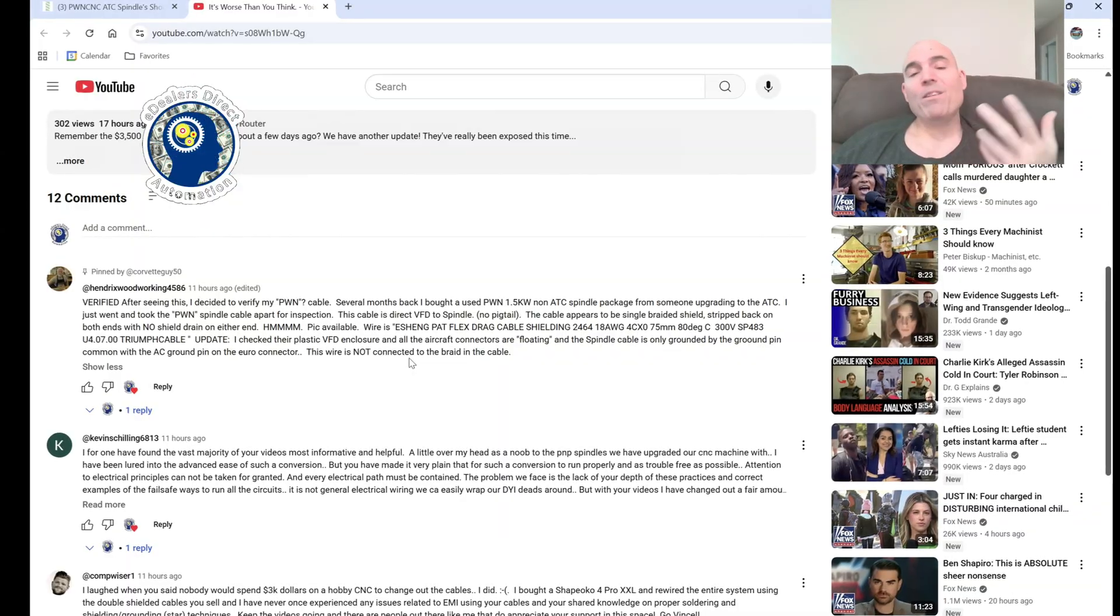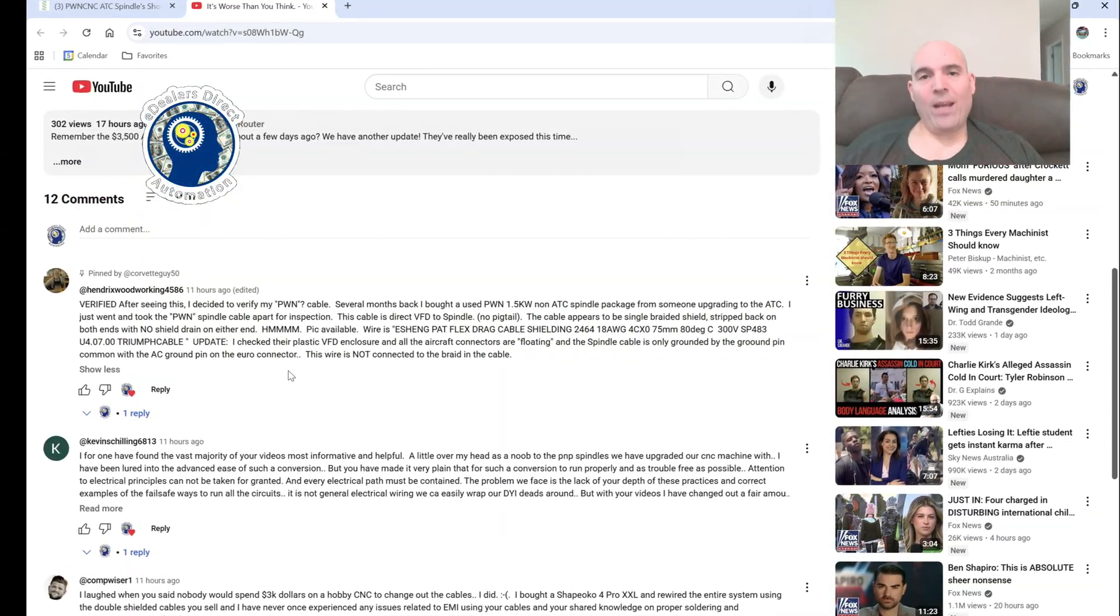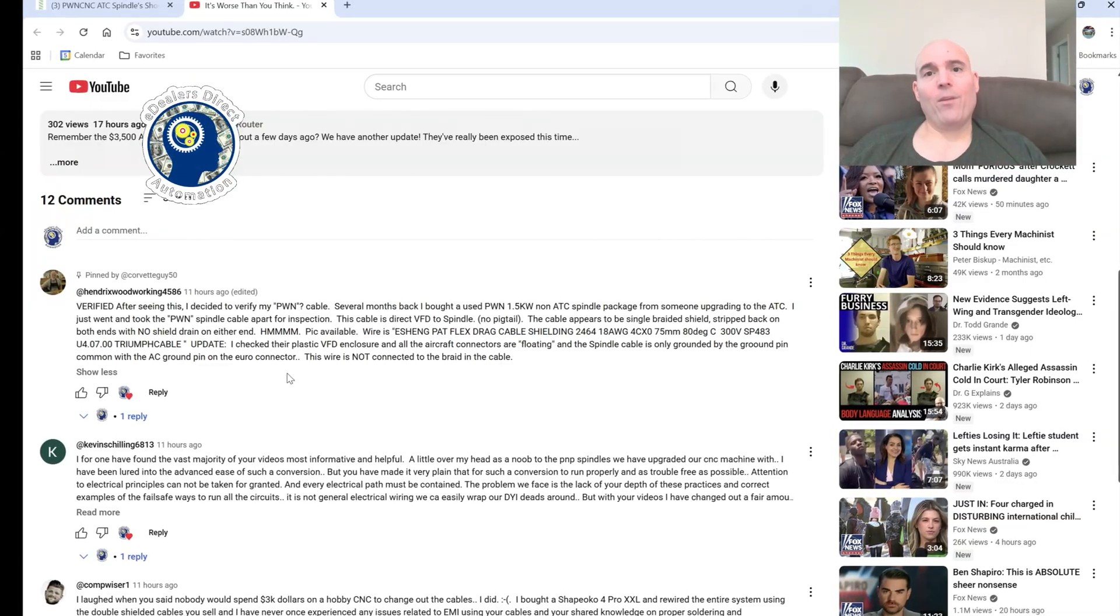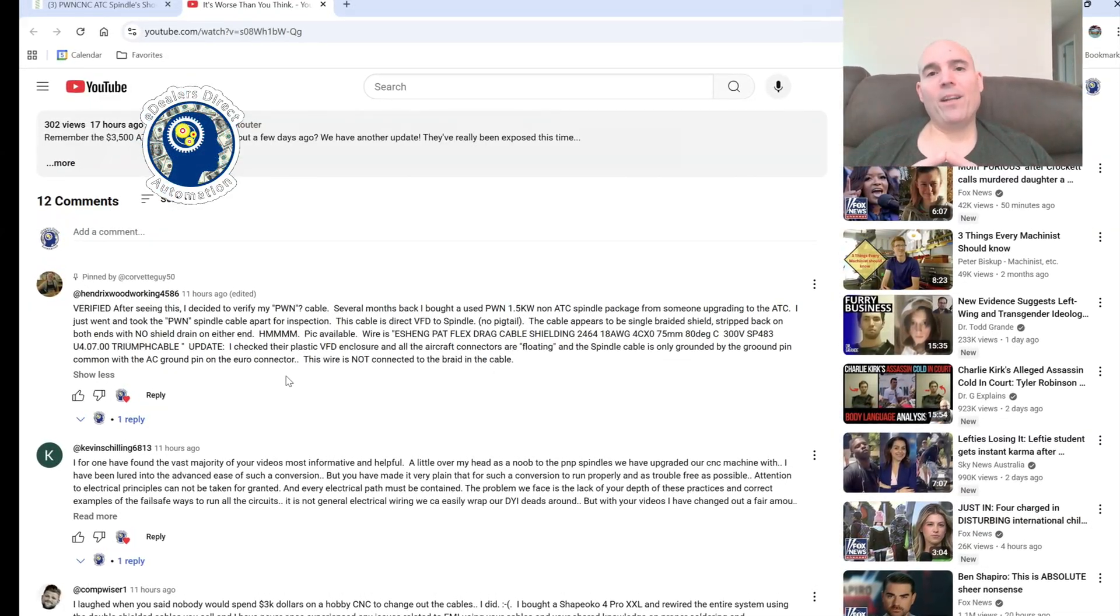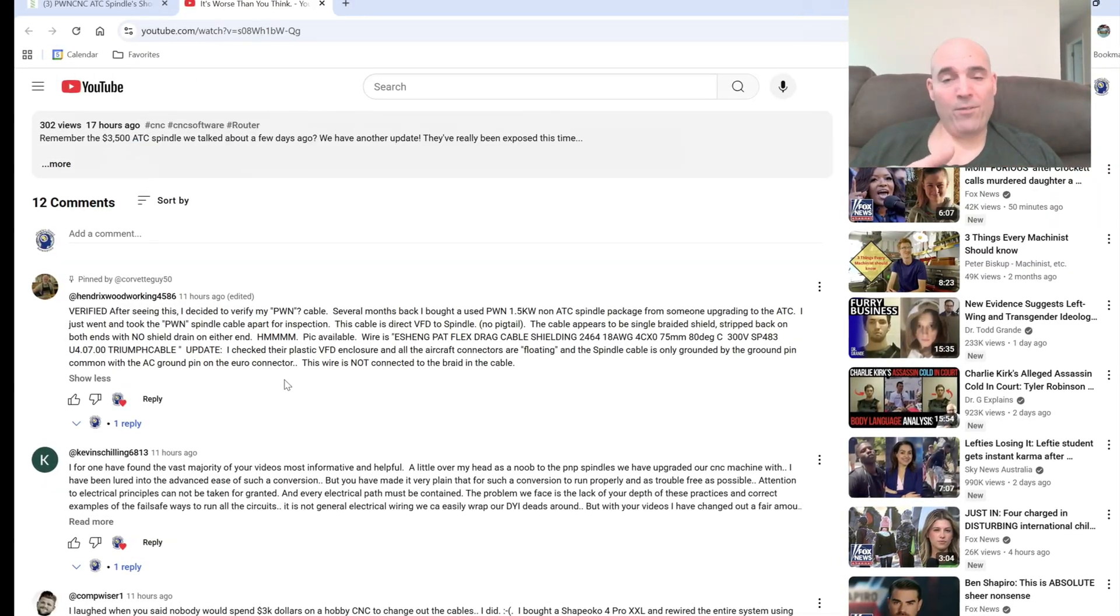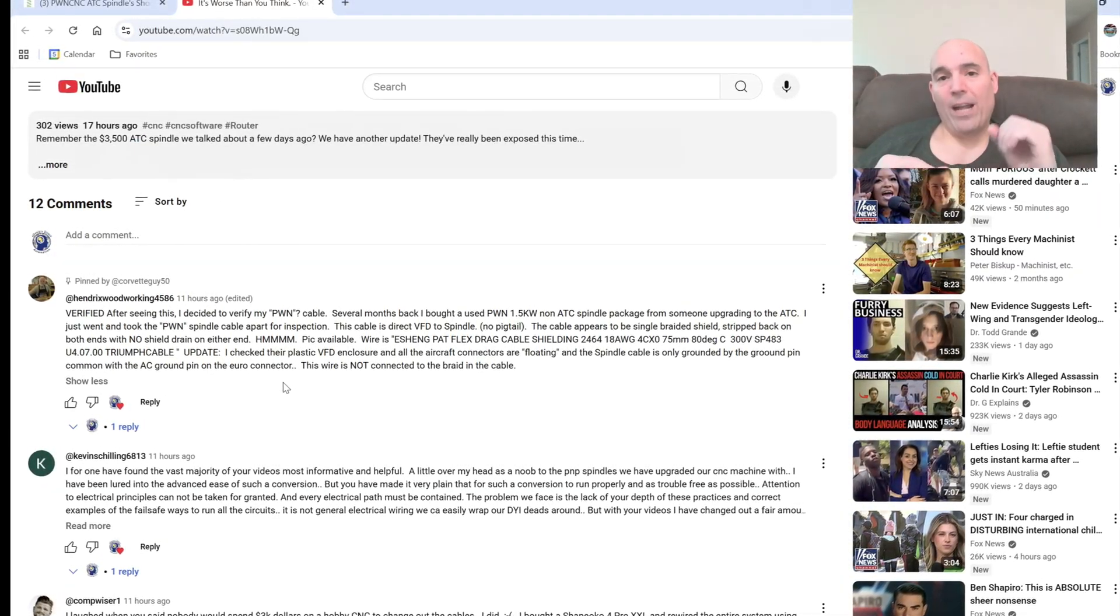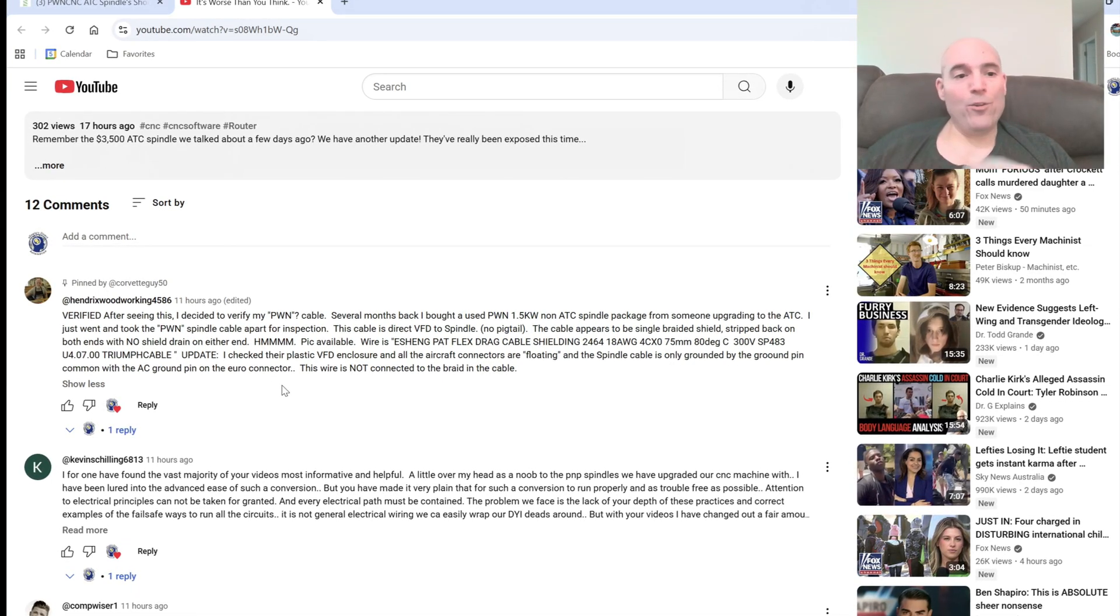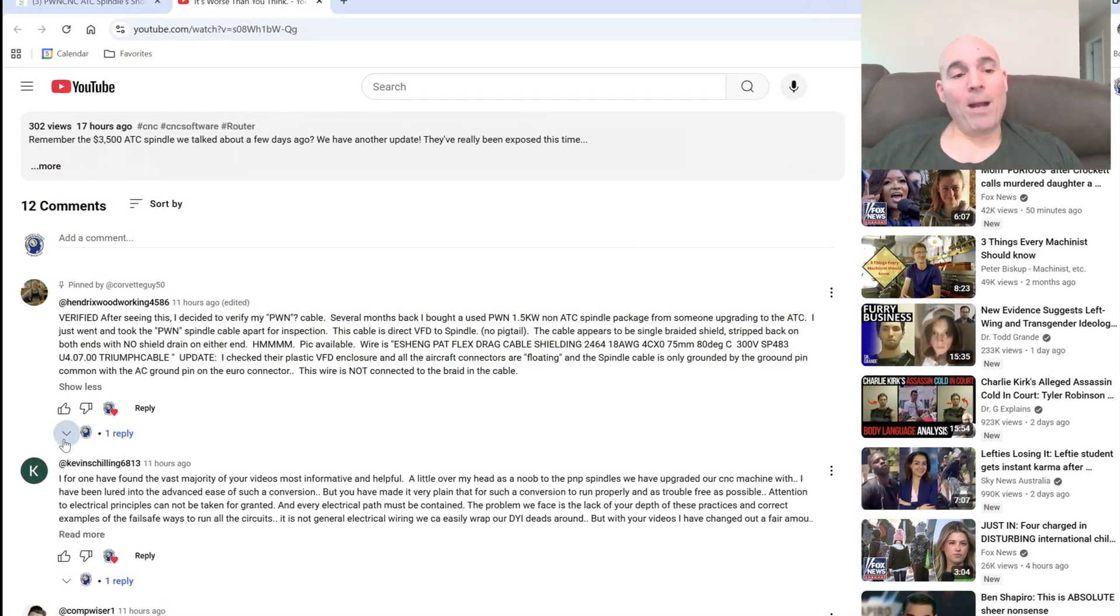I mean what are we talking about here, guys? Essentially he's telling you—and I will show you pictures to confirm this—that the cable on both ends has no shield drain attached and nothing is attached to that ground if it's even present in the VFD, which I don't believe it is. I think they're just connecting it to like he said that euro connector.